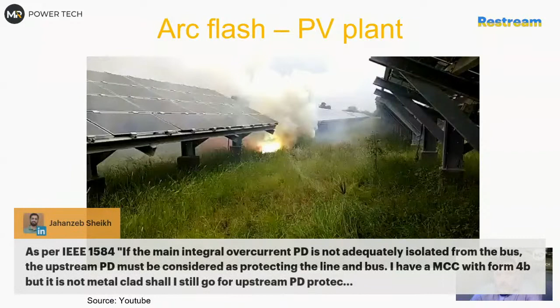Let me check. So, question again. Okay, you wrote a long question, so I can show it, but I have to hide it here to read it. So, as per IEEE 1584, if the main integral overcurrent PD is not adequately isolated from the bus, the upstream PD must be considered as protecting the line and bus. I have the MCC with form 4B, but it is not metal clad, so I still go for the upstream PD protecting line and bus.